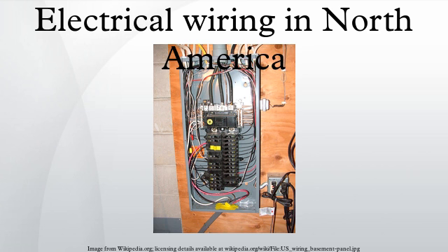Two-wire outlets having no grounding conductor may be protected by an upstream GFCI and must be labeled "no equipment ground." Most GFCI receptacles allow the connection and have GFCI protection for downstream connected receptacles. Receptacles protected in this manner should be labeled "GFCI protected." Most circuits have the metallic components interconnected with a grounding wire connected to the third, round prong of a plug, and to metal boxes and appliance chassis.